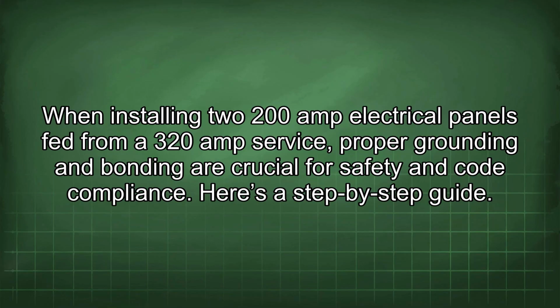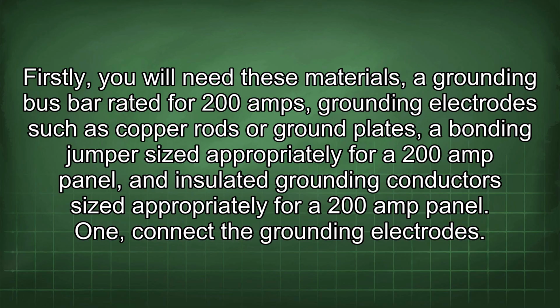When installing two 200 amp electrical panels fed from a 320 amp service, proper grounding and bonding are crucial for safety and code compliance. Here's a step-by-step guide. Firstly, you will need these materials: a grounding bus bar rated for 200 amps, grounding electrodes such as copper rods or ground plates, a bonding jumper sized appropriately for a 200 amp panel, and insulated grounding conductors sized appropriately for a 200 amp panel.